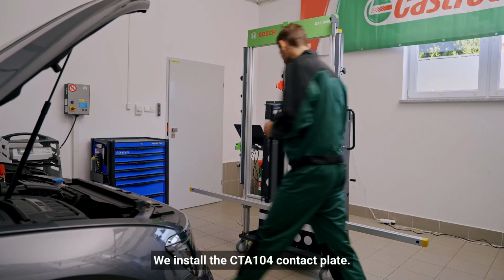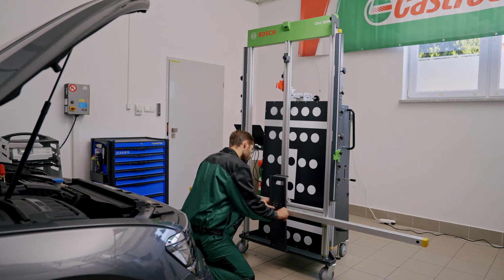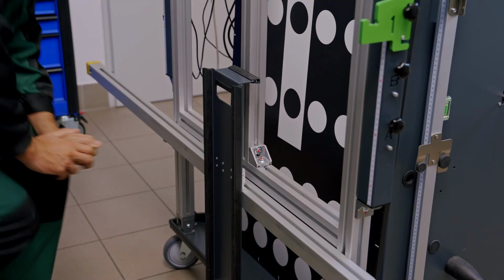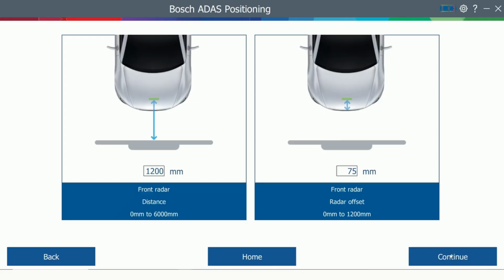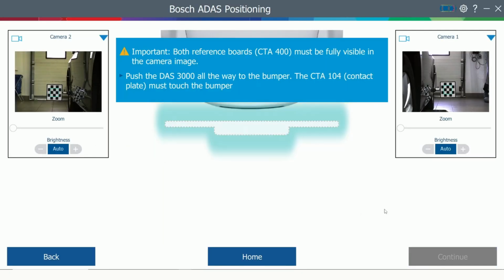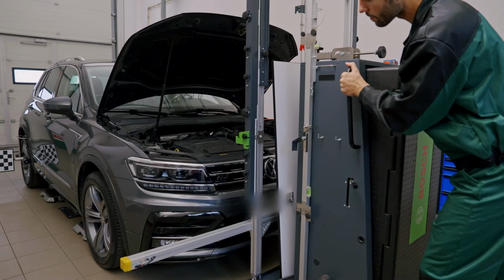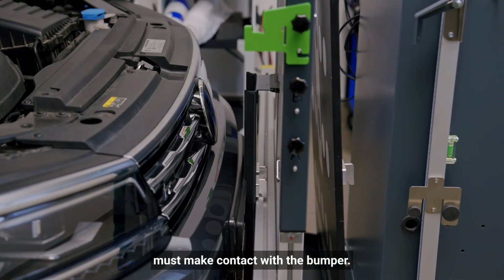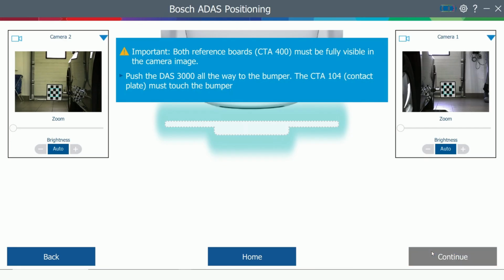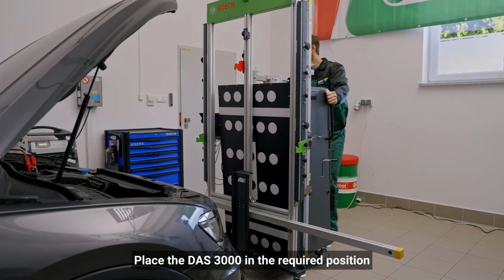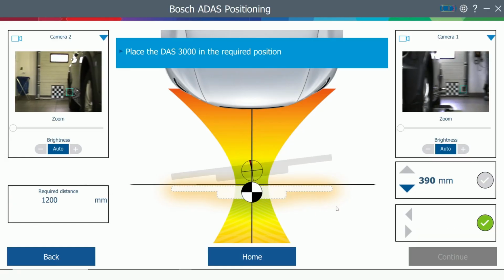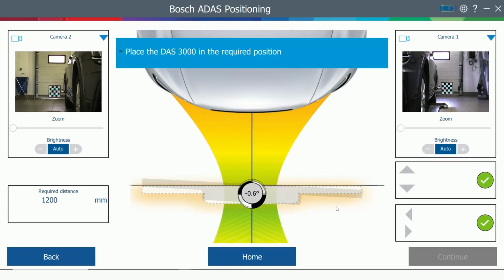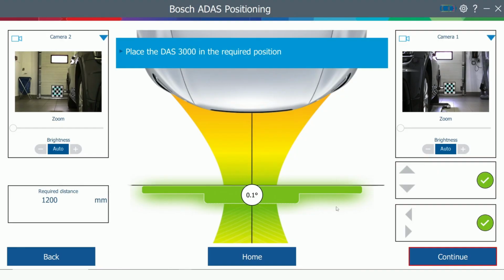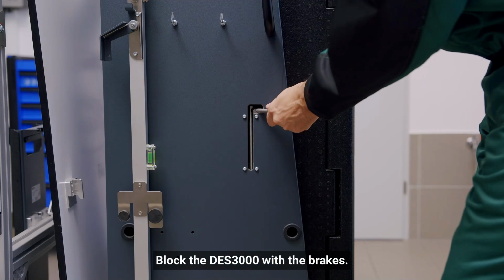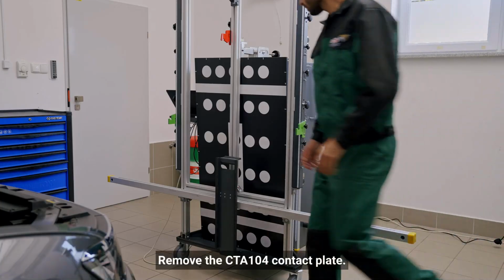We install the CTA 104 contact plate. Slide the DAS3000 up to the bumper. CTA 104 contact plate must make contact with the bumper. Place the DAS3000 in the required position, as on the computer screen. Block the DAS3000 with the brakes. Remove the CTA 104 contact plate.